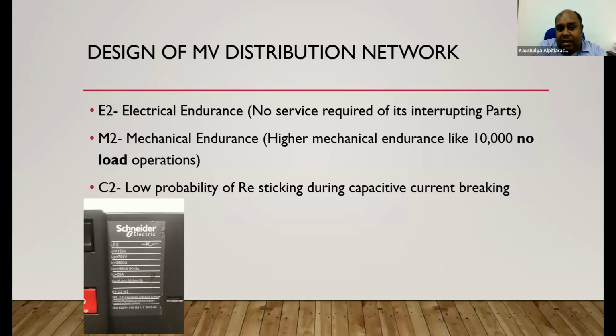M2, mechanical endurance. Higher mechanical endurance, like 10,000 tripping cycles at no load operations. C2, low probability of restriking during capacitive current breaking. Yes, that is called the avalanche breakdown. And when capacitive switching, if the utility goes and suddenly comes back, this scenario could happen. Just search for that. There are ample resources on the internet.